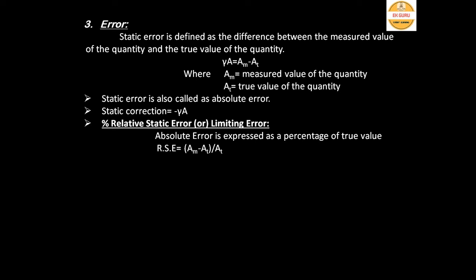When purchasing an instrument, the manufacturer provides the limiting error — that is the guaranteed error — expressed in terms of limiting error or as absolute or relative static error. The relative static error is equal to (Am − At) / At, meaning the static error expressed as a proportion of the true value.